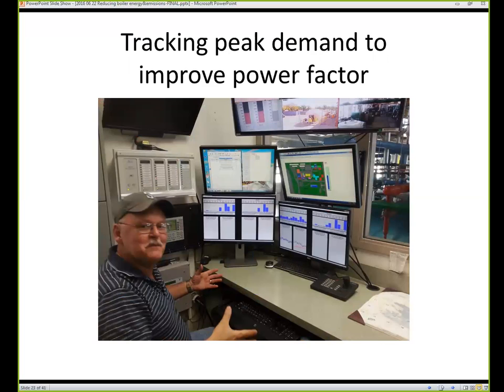Okay, what you're looking at here is a screen that we have up in the front office, and we're able to look at everything that we have in the plant and the hospital. You have Veeder-Root underground storage tanks on the left screen, top left. You have the building management, top right screen. And you also have the boilers, which are coming off Chesil recorders on the bottom screens. They give you your O2, your flow of steam, flow of water, and you have graphs. And those are being recorded to the hard drive.